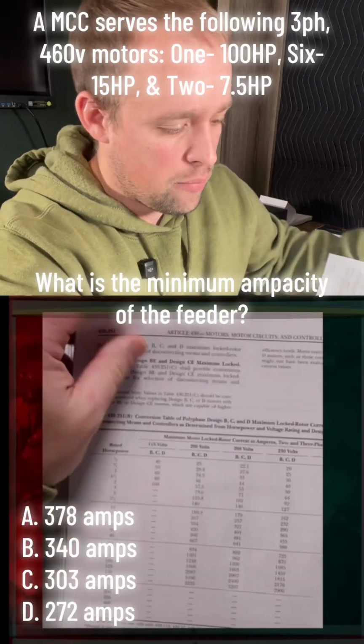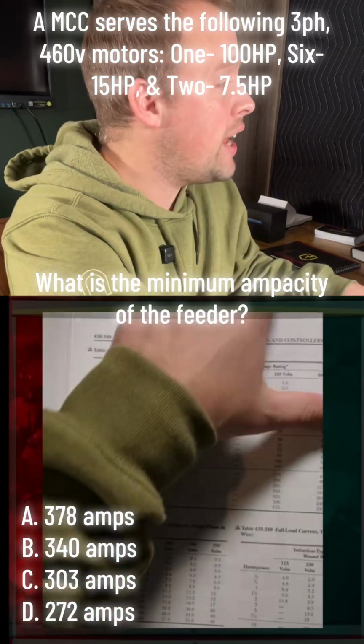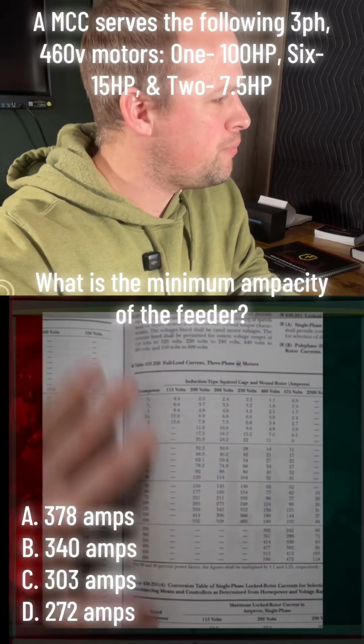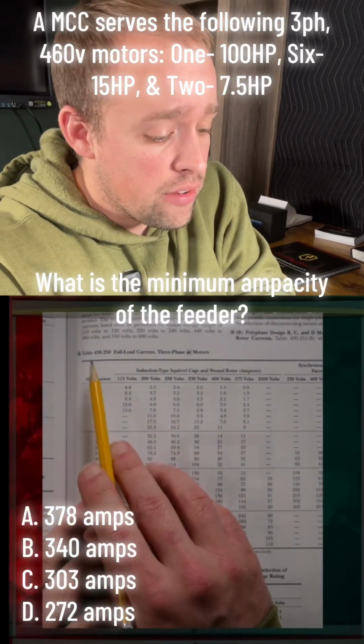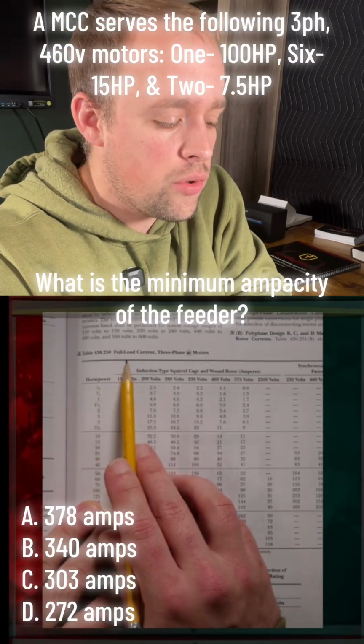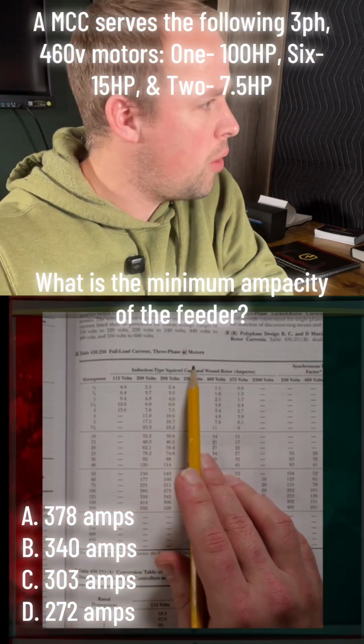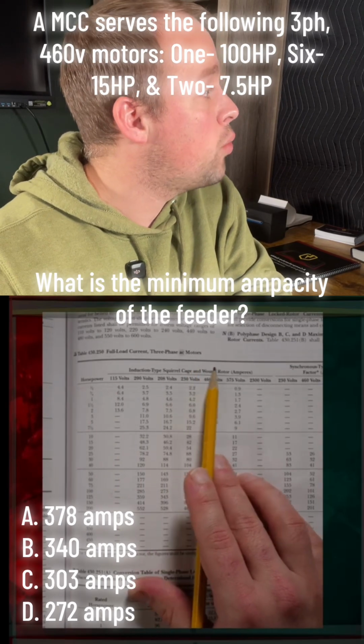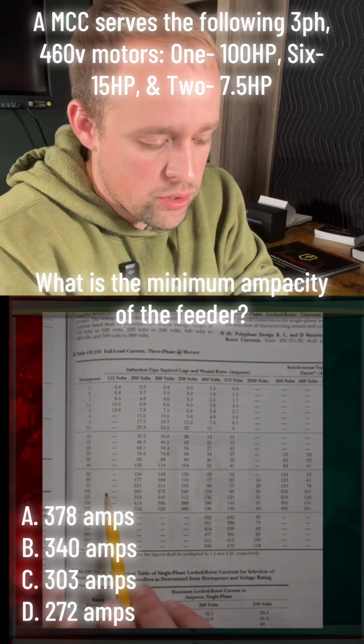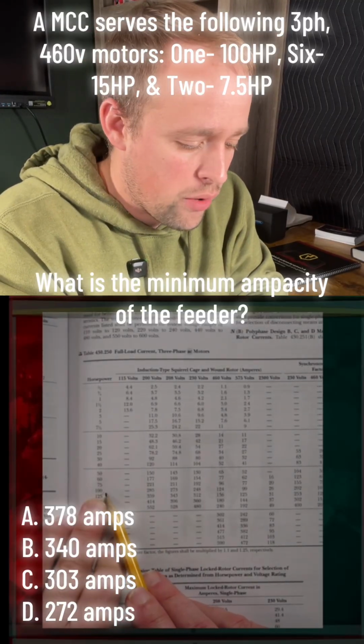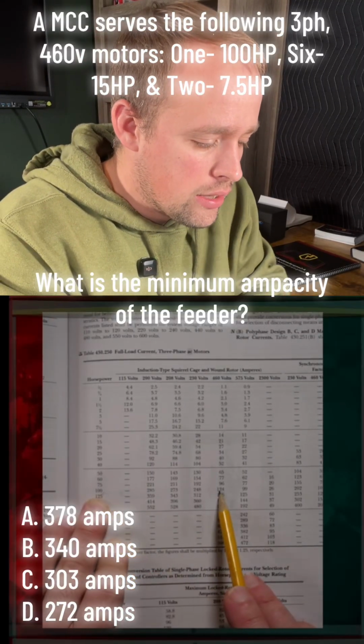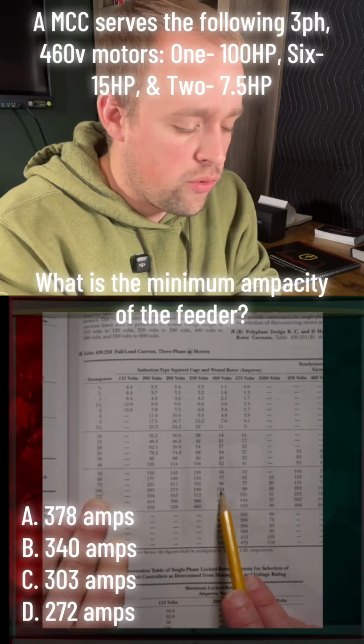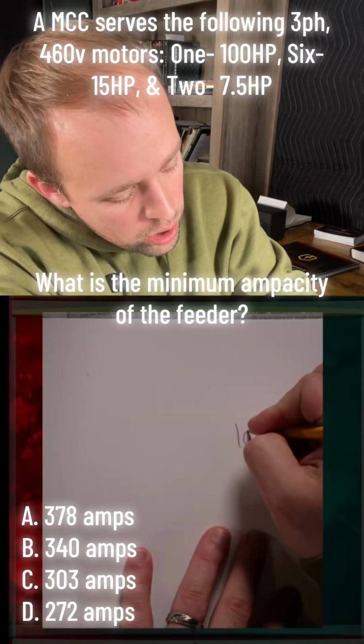Hopefully I have a piece of paper. I do. So I'm going to have to write down some ampacities here, okay? So going here, as we can see, 430.250 tells us the full load currents for 3-phase AC motors. So our first motor in question says a 100 horsepower. So that's right here, 100 horsepower. That's my row. Now my column is 460 volts. So 124 amps is what I'm going to have for this 100 horsepower motor.